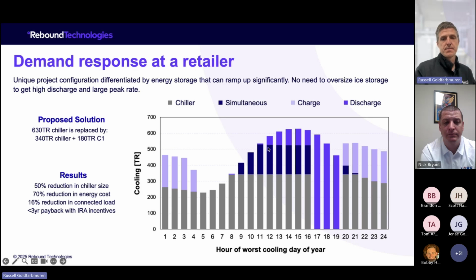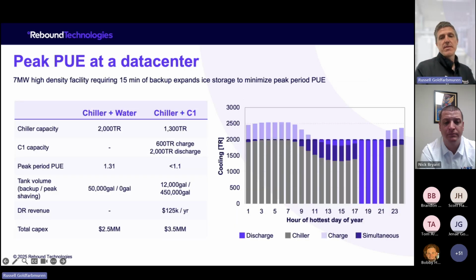So we can reduce energy costs by 70% and drop the capex of the total system by peak shaving the rest of the time. To look at a data center, here we have a flat load. Similar, what we're doing here is a resiliency play. So we deliver 12,000 gallons of ice storage that gives them 15 minutes of full facility backup cooling in case of a power failure. And then we're able to deliver this huge demand response asset as well that allows them to interconnect into the grid a lot easier because their connected load is reduced during that peak period. And that offers them a lot of benefit.